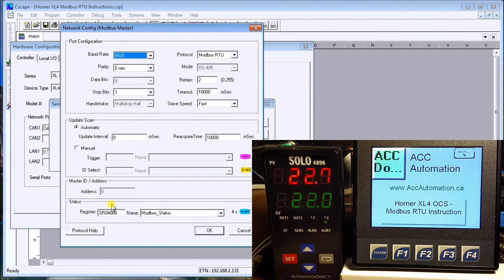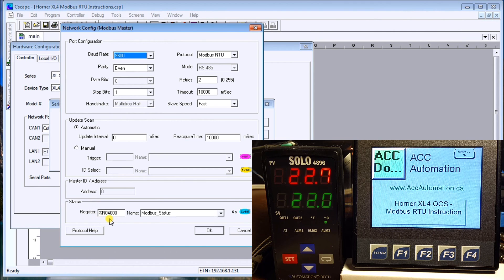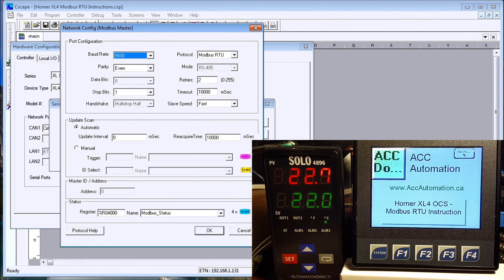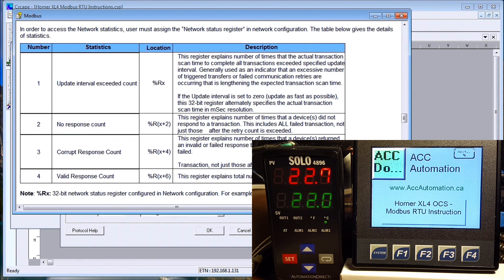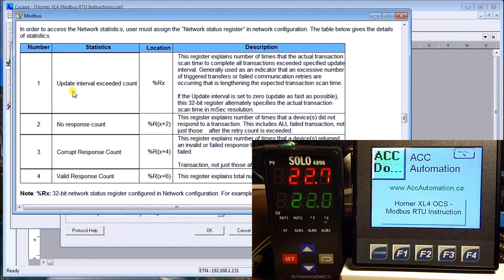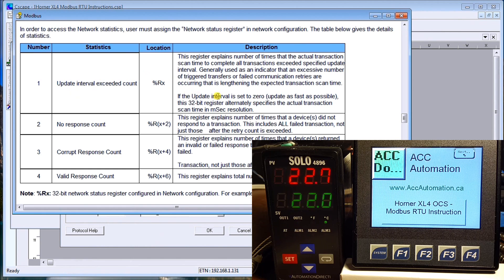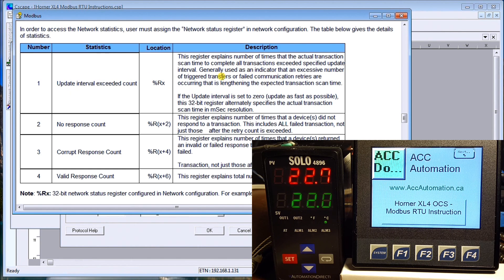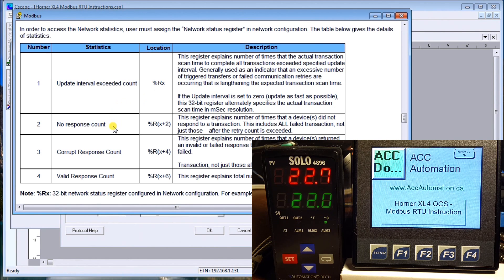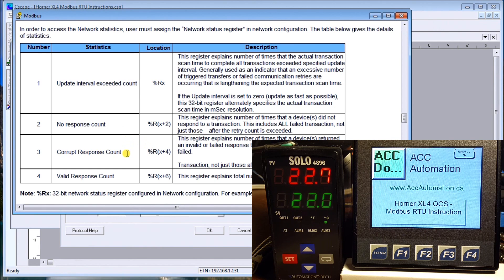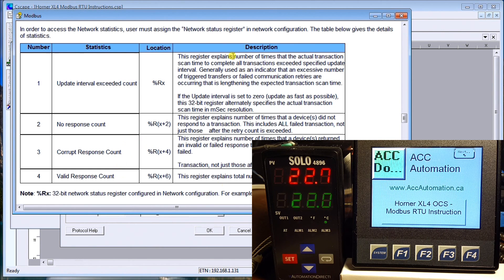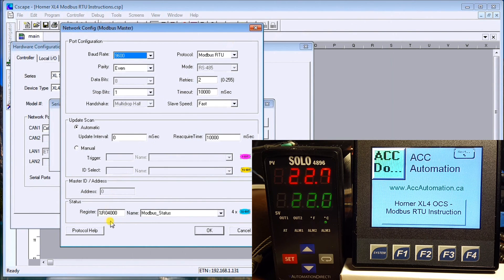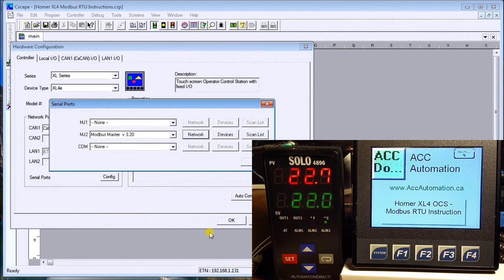We have a status register at R4000 which gives us our Modbus status. If we refer to the help menu, it will show you the first register gives you the milliseconds that the last scan time was, then you have a no response count, corrupt response count, and a valid response count. These are automatically updated from that one setting that we just set, which was the R4000. Then we have devices.